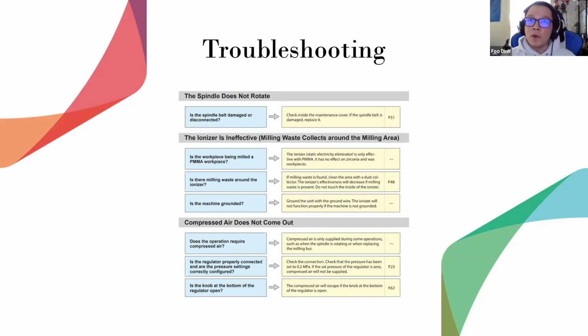What I often see is customers don't tighten the relief valve on the bottom of the regulator all the way. And when you don't tighten it all the way, all the air is just going to escape no matter what you do. Or they have poor wall connections. Most of the time, labs have compressors in different rooms, and they're running copper tubing or hoses throughout the office for these connections. If the air's leaking from that connection, we're never going to get consistent air pressure, so check for leaks. Make sure the knob on the regulator is pushed down and closed after making an adjustment. If it's up, as it's milling, it's just going to slowly rotate and adjust the air pressure again.